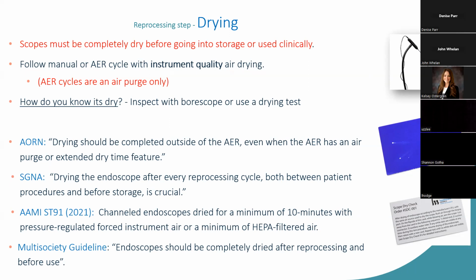It's important with any process to have some embedded quality control, at least periodically. How would you do that with drying? There's what's called drying verification tests. Yes, you could put a borescope down the channel of a scope and look to see whether you have residual moisture, but then you'd have to reprocess the scope. The cards that you see on the screen look like a business card with the instructions.